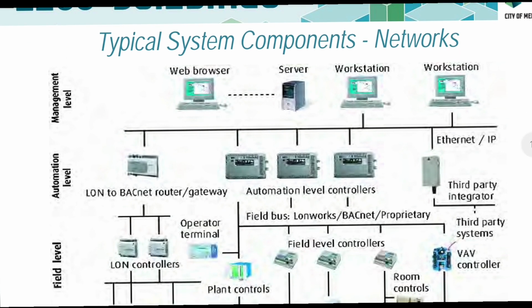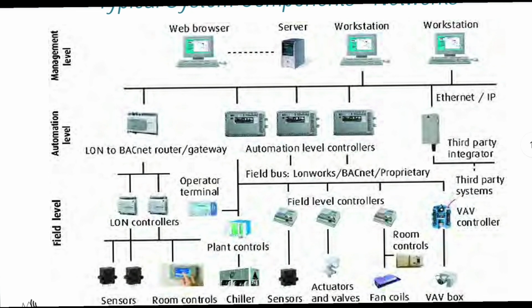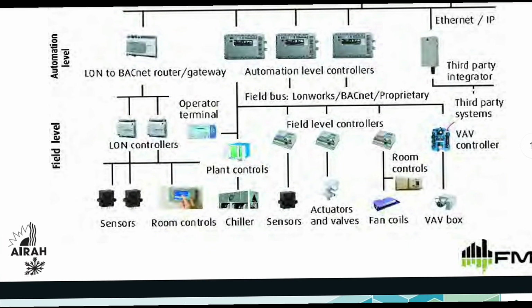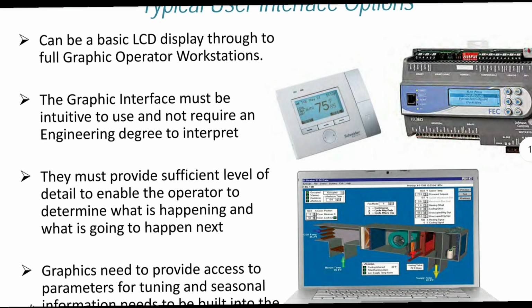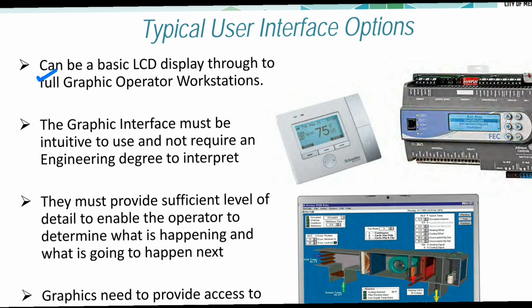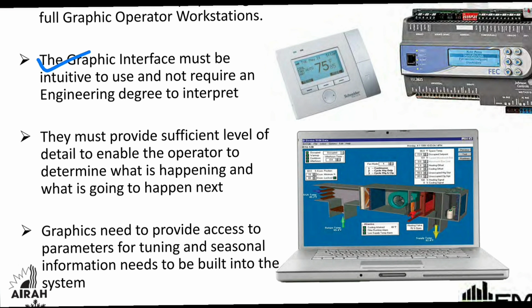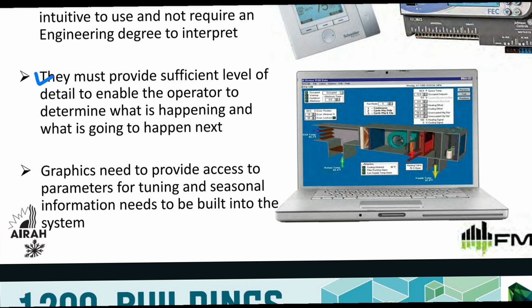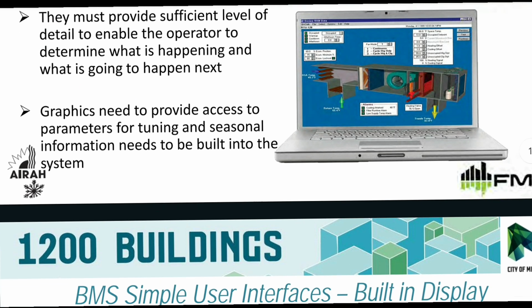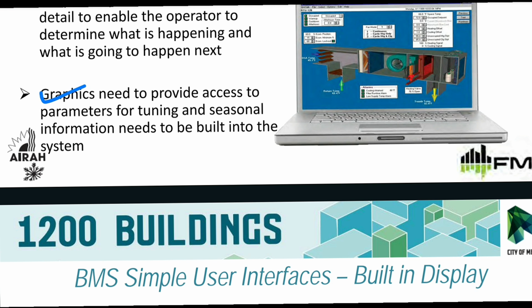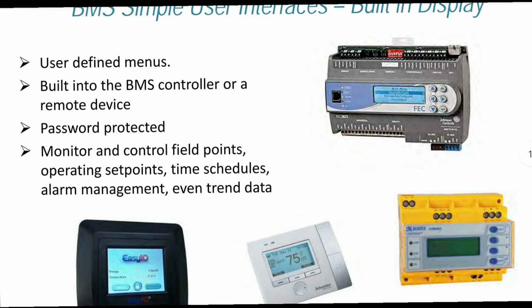All connect to a DDC panel like the BMS panel. Typical system components and networks: first, a web browser connects to the server workstation. After that, the workstation connects to the integration network. Typical user interface options can range from a basic LCD display to a full graphic operator workstation. The graphic interface must be intuitive to use and not require an engineering degree to operate. It must provide sufficient detail to enable the operator to determine what is happening and what is going to happen next. Graphics need to provide access to parameters for tuning, and seasonal information needs to be built into the system.